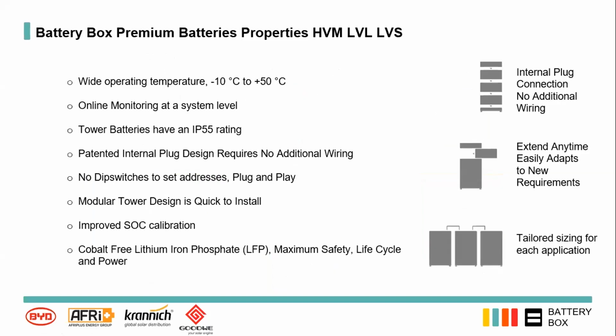So here we have some of the common properties of the premium battery range. They've got a really wide operating temperature. They can operate from -10 to +50 degrees centigrade, and they can operate at full power with no power derating between 5 degrees centigrade and 50 degrees centigrade, allowing a lot of flexibility in terms of where it can be installed.